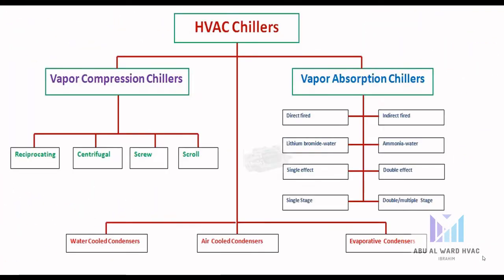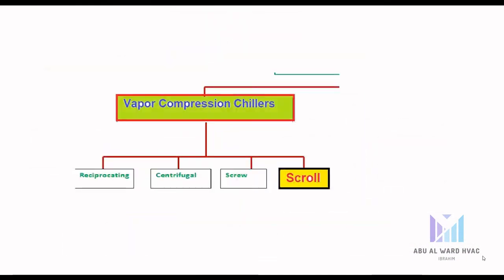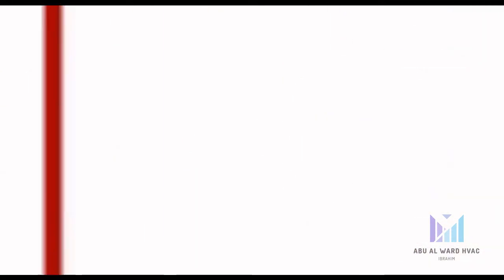Screw compressors are another type of positive displacement compression: as the screw rotors turn, the gas is compressed. They have one or more rotors to accomplish the compression. Positive displacement compressors are best suited to handle smaller volumes of refrigerant gas over high compression ratios. The HVAC industry is trending to phase out reciprocating compressors, favoring screw and scroll. Screw compressors are used in the 70 to 500 ton range and in both water-cooled and air-cooled chillers.